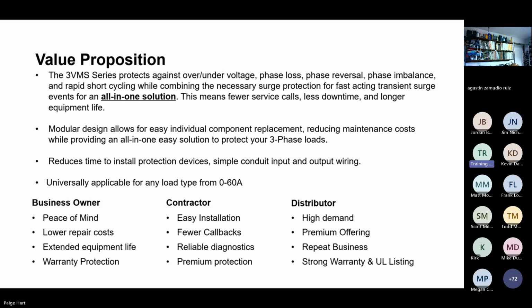Modular design allows for an easy individual component replacement. This is another thing that you can't do, for example, with something like a product that has a circuit board on it that does all the work. This one, each individual component is replaceable in and of itself. This again helps the contractors to be able to service the equipment without having to replace the whole box. This all-in-one solution reduces time of installation, it protects devices, and you have simple conduit input and output wiring.